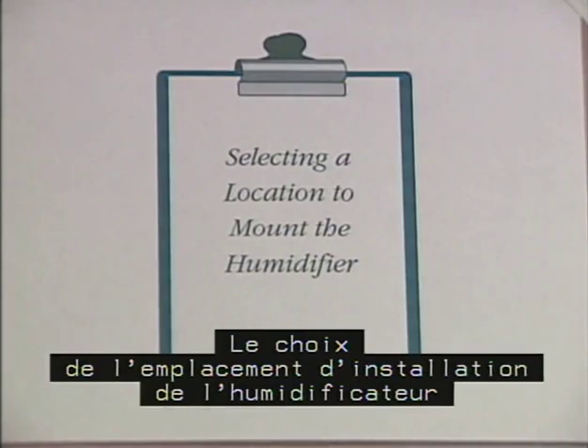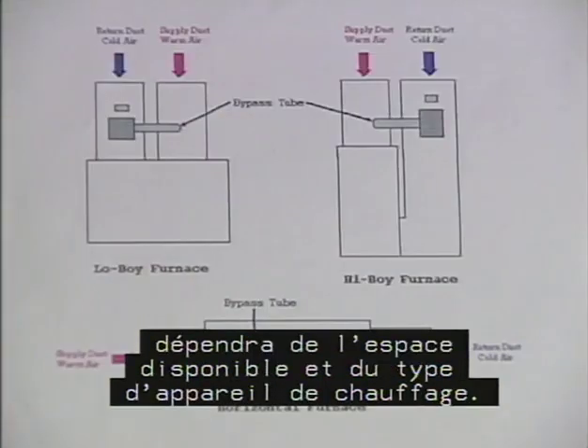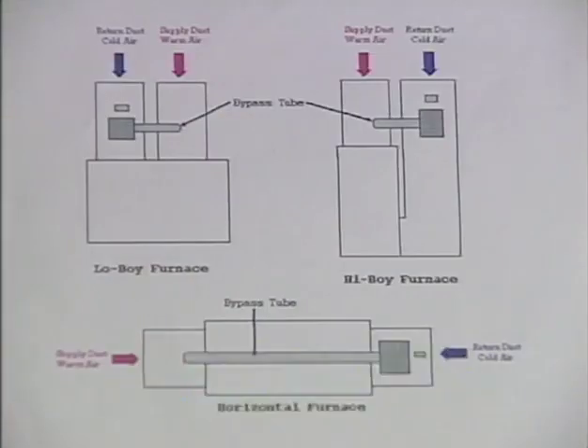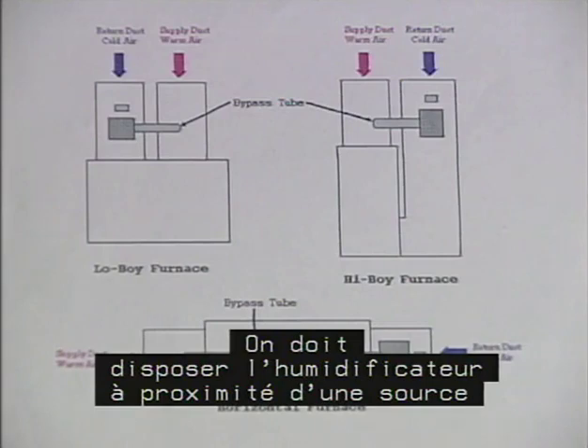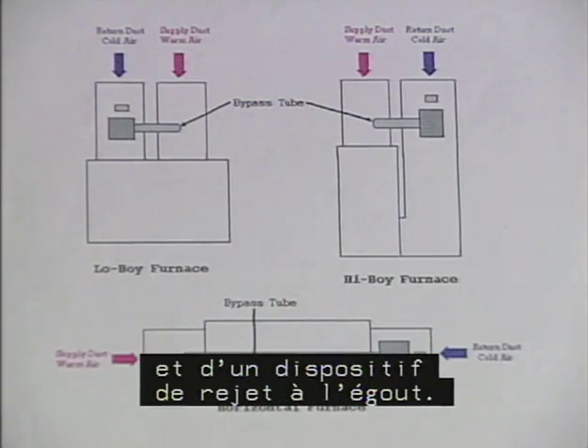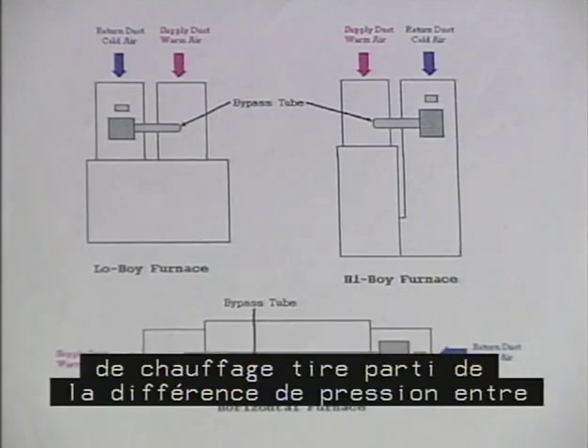Selection of a location to mount the humidifier will depend on available space and furnace type. The selected location should be near a water supply, an electrical outlet which cannot be switched off, and a drain. Bypass-type furnace humidifiers rely on the pressure difference between the supply duct and return duct to create an airflow that forces air through the evaporator pad.